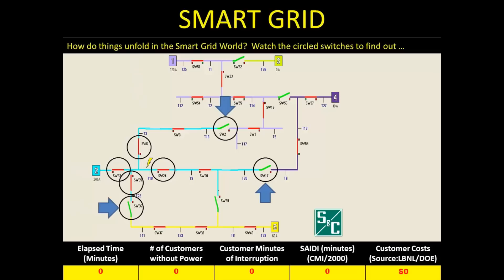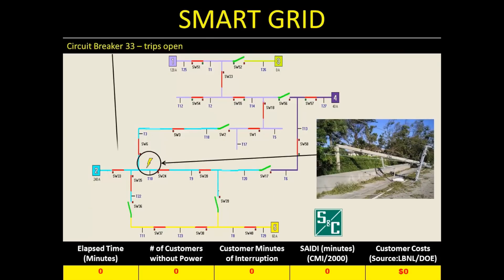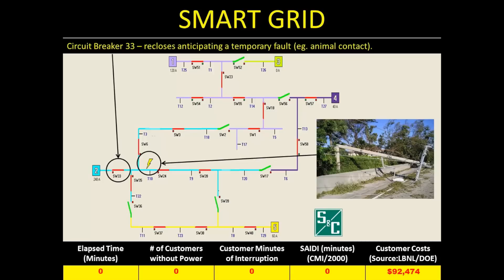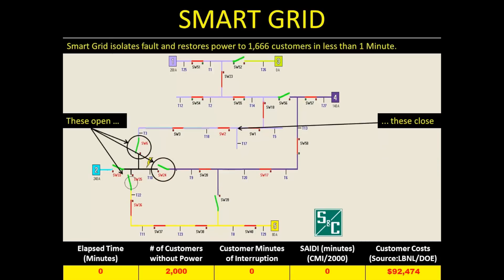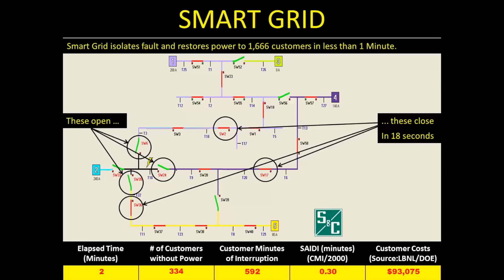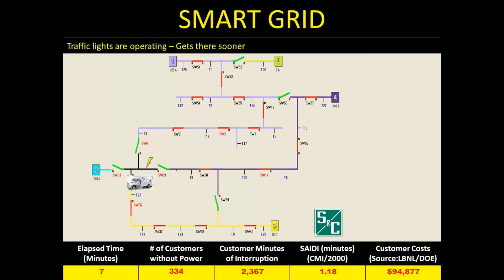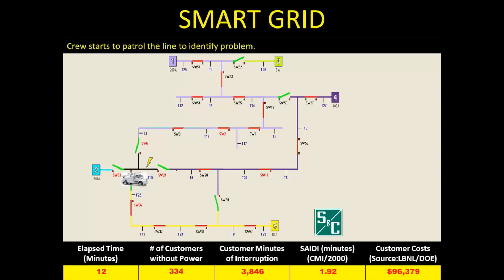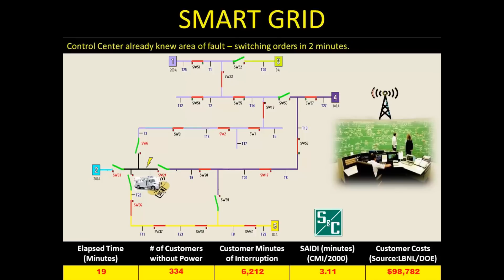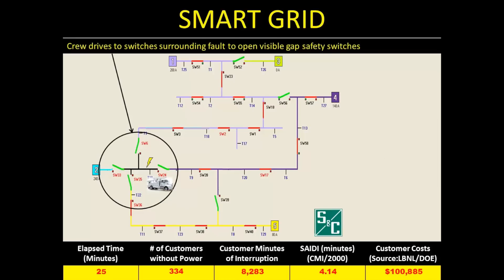We are going to have the same outage — interrupted by the circuit breaker the same as before. The breaker recloses hoping the fault is transient, but finds it's still there and locks open. Then the smart devices talk to each other, isolate the fault, and close back in to restore power in just 18 seconds. The smart devices also send a message to headquarters alerting them to the problem location so headquarters can dispatch a crew, which can move more quickly because far fewer traffic lights are out. The crew patrols a much smaller line segment, so patrolling time is much shorter.